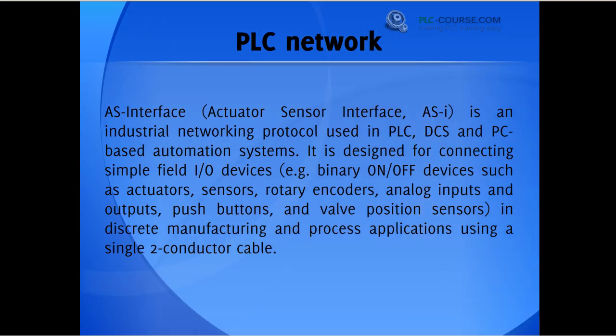For those of you who don't know what an ASI link is, the full name is Actuator Sensor Interface. This is an industrial networking protocol used in PLC, DCS, and PC-based automation systems. It is designed for connecting simple field input/output devices in discrete manufacturing and process applications using a single two-conductor cable.